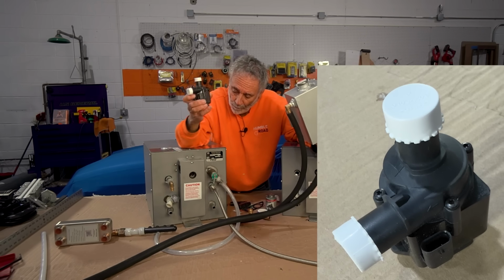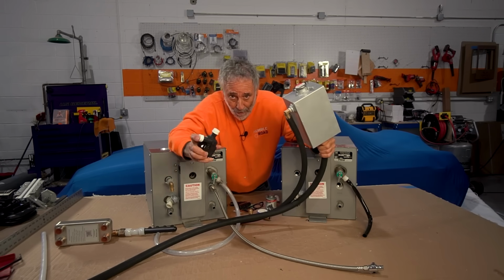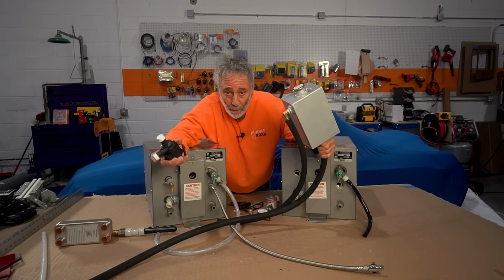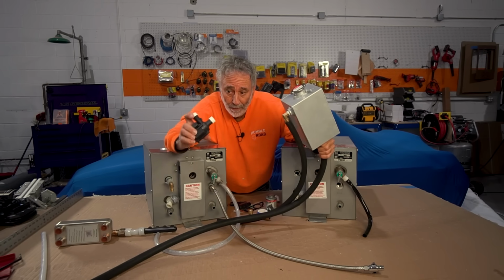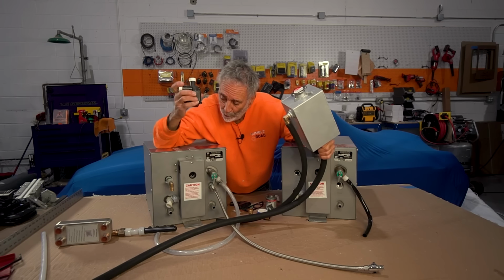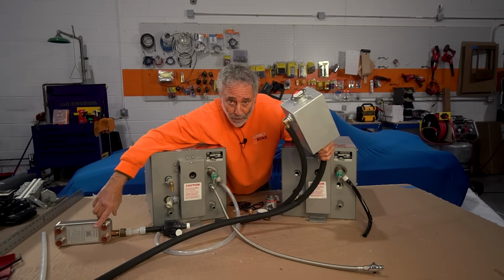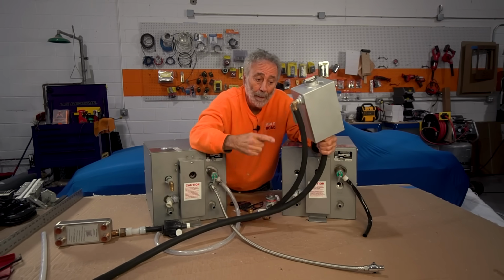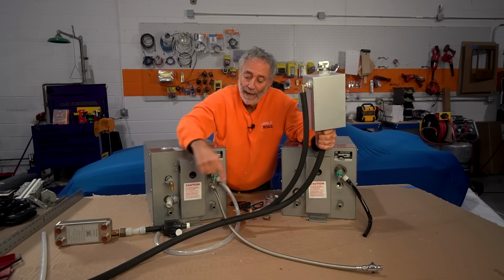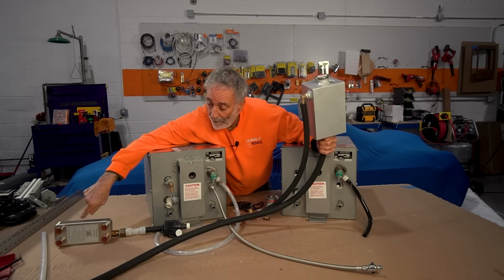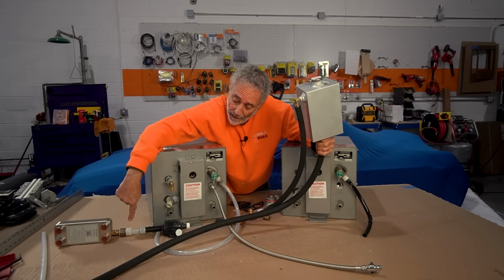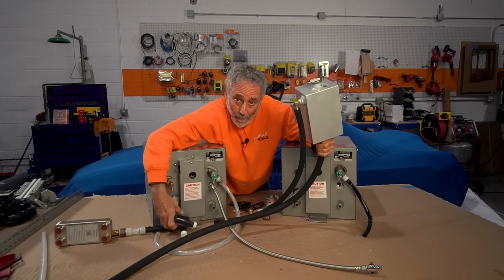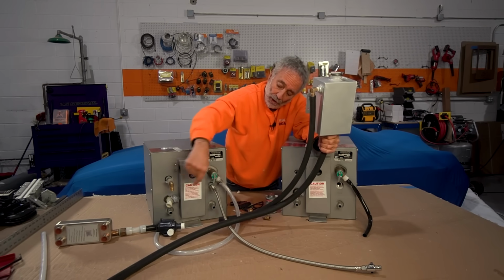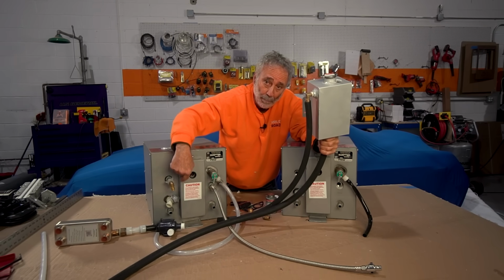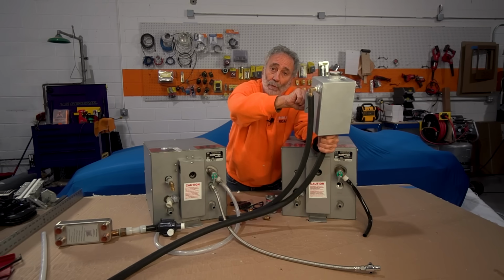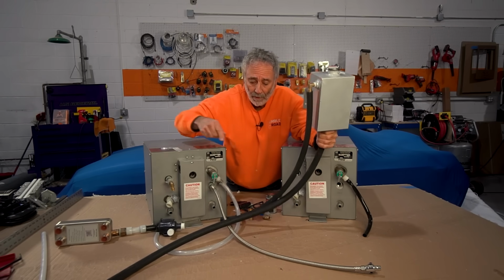Bosch water pump. When I say water pump, this is designed to pump glycol, 200 degree antifreeze, no worries there. I put this pump after the heat exchanger on the way back. So head pressure, which is gravity, takes me all the way down and through the heat exchanger, then it trickles out this way. The pump picks it up, pushes it through my water heater, makes hot water, puts it back into the reservoir. Closed loop system.